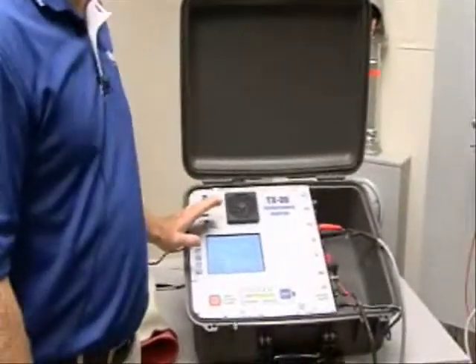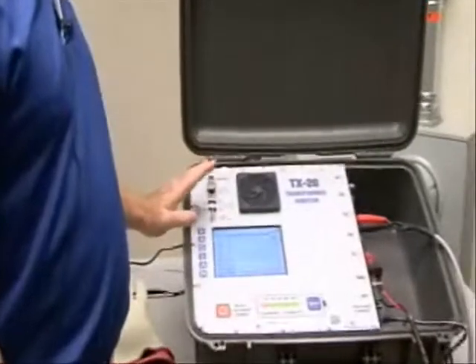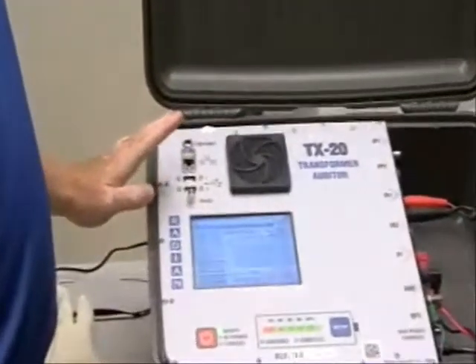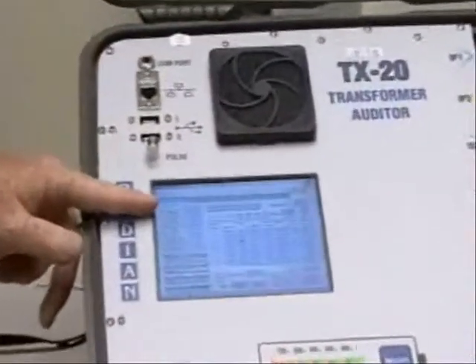Okay, returning back to the screen of the TX Auditor, the measurements that we're going to be making are all related to phase A of this service. I can see the voltage that I'm measuring is at 121.8 volts. The current coming from the CT is 0.1 amps. The phase angle for voltage and current is 30 degrees, and the power factor of that is 0.86. I can show my instantaneous watts being 10.69 watts, and my VARs being minus 6.3 VARs.